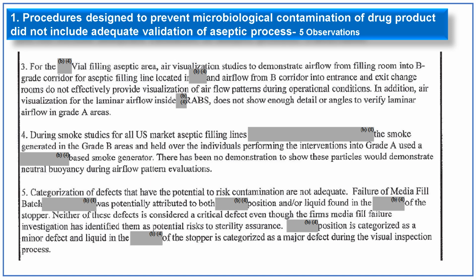The fifth and last point in the first 483 is that the categorization of the defects that have a potential risk of contamination is not adequate. So there was a media fill failure, and it was attributed to both the position and the liquid found in the stopper. Neither of these defects is considered a critical defect, even though the firm's media fill failure investigation has attributed it as a risk to the sterility assurance. The position in the stopper is categorized as a minor defect, and the liquid on the stopper is categorized as a major defect during the visual inspection.